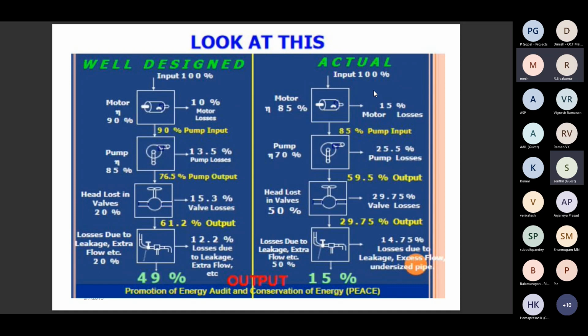This is also a pump example, comparing a well-designed system with the actual design, with various associated losses. In the well-designed case, motor efficiency is 90%, pump efficiency is 85%, and the head loss due to throttling is 20%, plus some leakage. In the actual existing system, motor efficiency is 85%, pump efficiency only 70%, and the head loss is 50%, compared with only 20% in the well-designed one. Comparing both, well-designed pumps consume far less energy than the existing ones. So you can select proper pumps and motors for the particular application, since throttling leads to more energy consumption. Wherever needed, a VSD can be adopted to reduce the speed according to flow control.